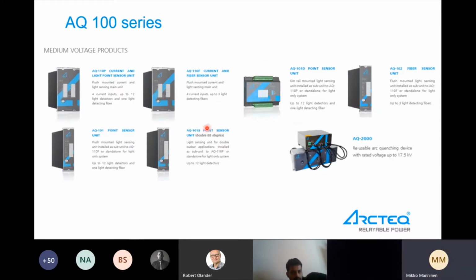And then there is a special device which is called 101S. This is for more complex systems, for example, double bus bars and duplex switch gears. And we have some standardized schemes for these. This device has more binary inputs for these special schemes. 102 fiber sensor unit has 3 light detecting fibers.